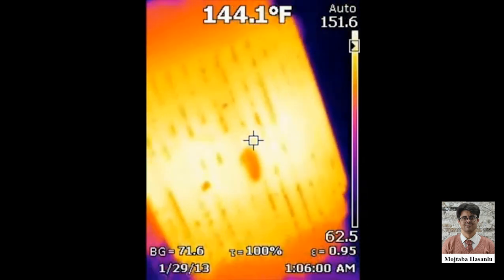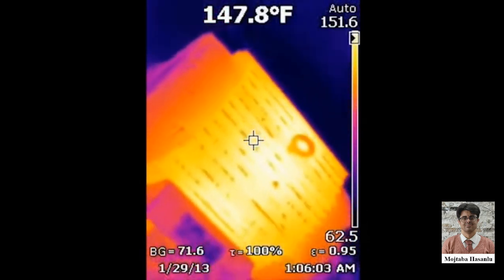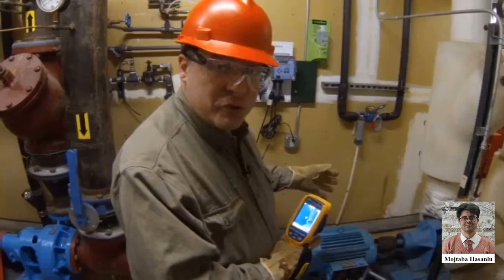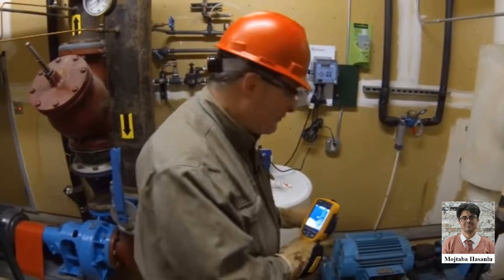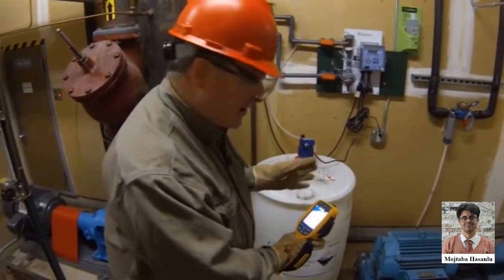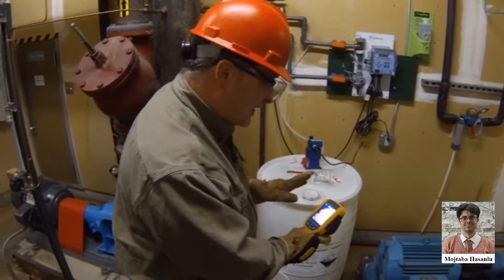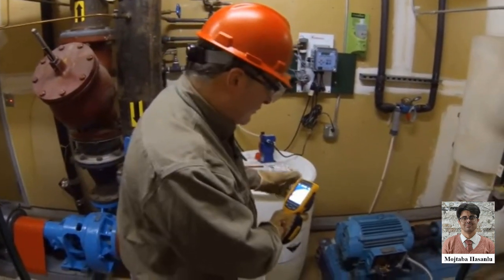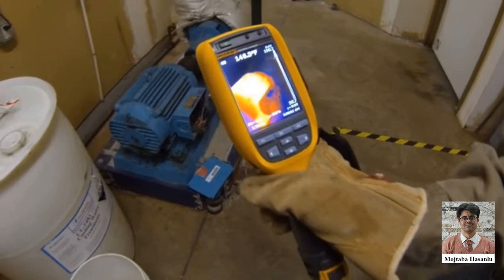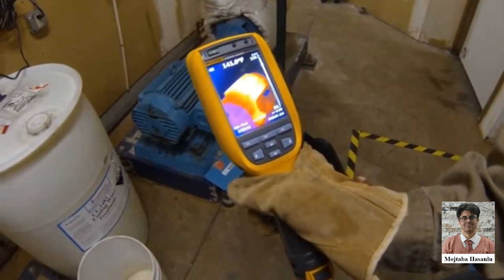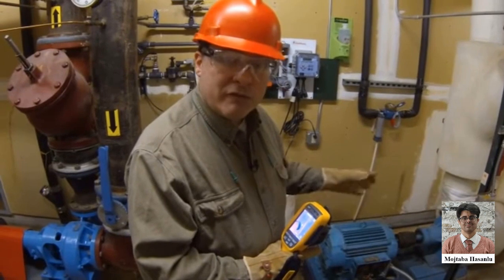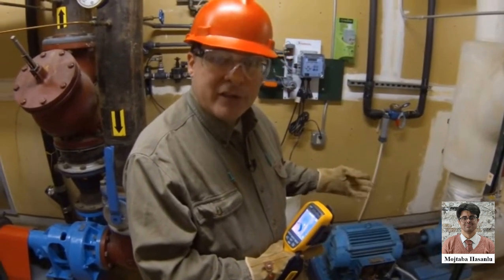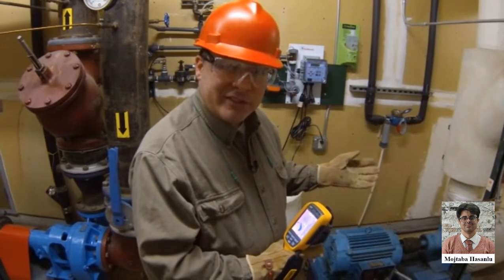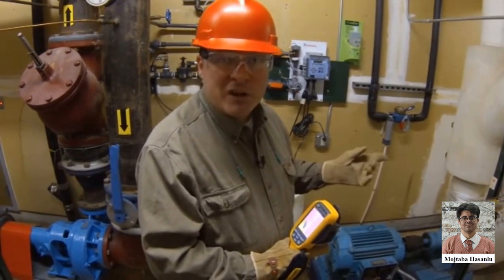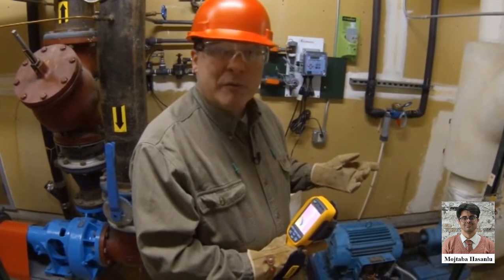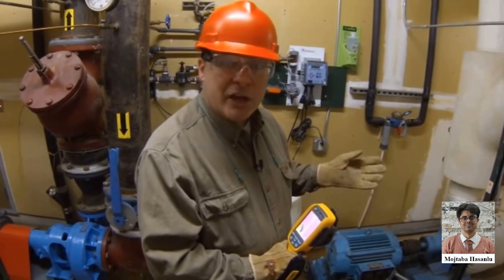Looks quite even, I don't see any issues there. Obviously, if this motor were running hotter than usual, that could be an indication that perhaps the cooling fan's not working properly, it's not aspirating properly. I think everything's working okay here. Number one, because the temperature is good. Number two, the fan is operating. If I do find a localized hotspot, that could be indicative of a problem with one of the phases. Maybe some of the windings are burning out. Too much heat will destroy that insulation. Could also be an issue with transients on the line. Could be a problem with harmonics on the line causing unusual heating.